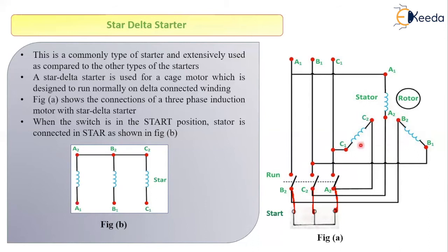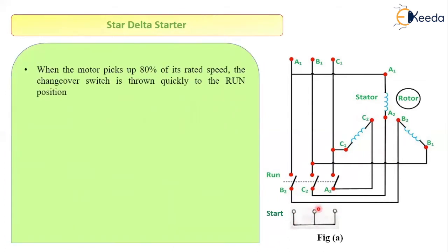In this condition the stator of our induction motor will be connected in star, just as shown in figure B. Initially the connections are such that our stator is connected in star. Once the motor picks up about 80% of its rated speed, the changeover switch will be thrown to the run position.